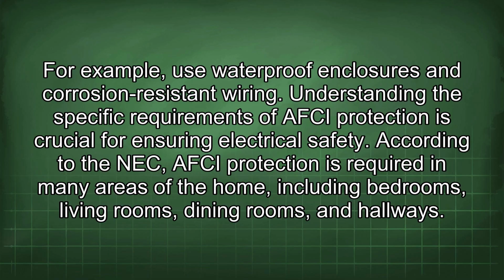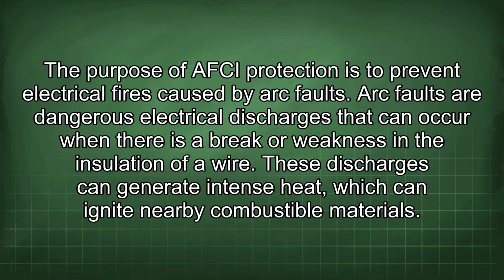Understanding the specific requirements of AFCI protection is crucial for ensuring electrical safety. According to the NEC, AFCI protection is required in many areas of the home, including bedrooms, living rooms, dining rooms, and hallways. The purpose of AFCI protection is to prevent electrical fires caused by arc faults. Arc faults are dangerous electrical discharges that can occur when there is a break or weakness in the insulation of a wire. These discharges can generate intense heat, which can ignite nearby combustible materials.